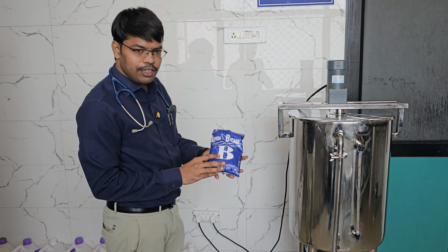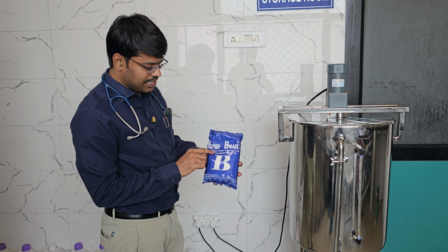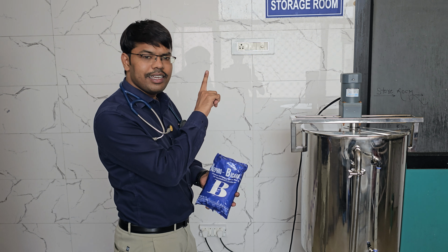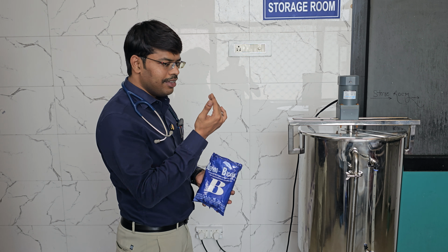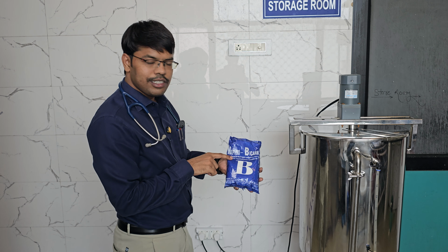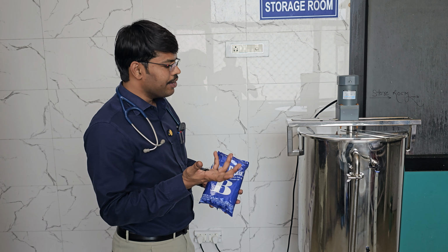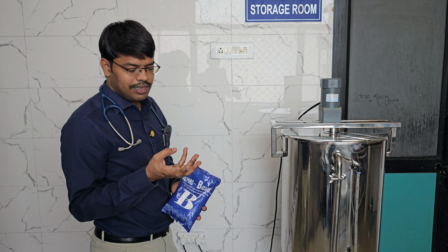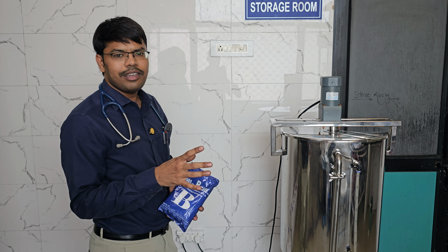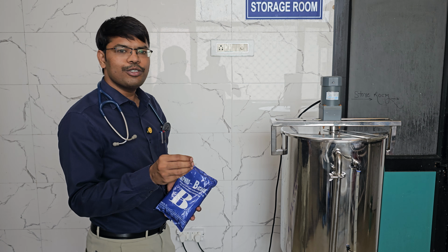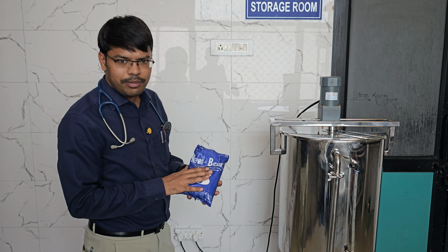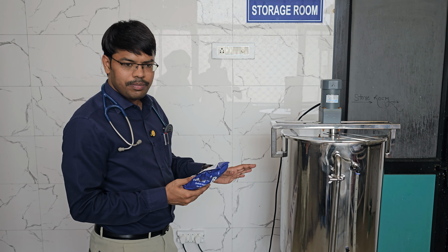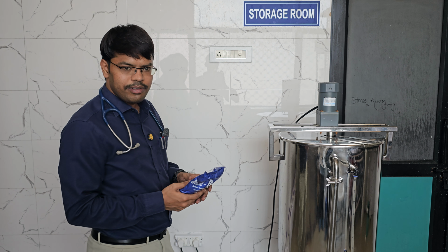Students, the nephrology residents, also had this doubt: this contains sodium bicarbonate, so sodium is also there. The final sodium that the dialysate delivers to the patient includes this sodium also. Another question: apart from soda bicarb, are any other formulations available? Acetate and citrate formulations are available, but in almost all places only soda bicarb is used because of the many advantages it provides. It is easy to prepare, manual, and we have seen this method.